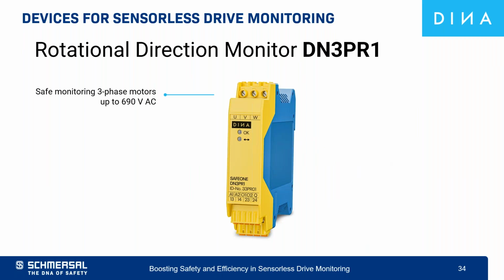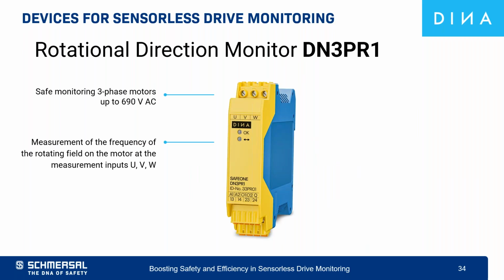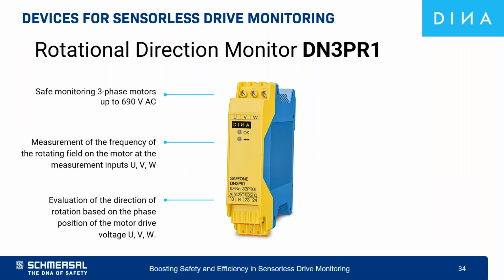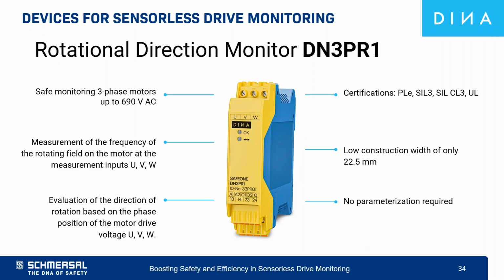This one can be used only for 3-phase motors. So you need all 3 phases due to the operational principle, because as Samuel explained already, we measure the frequency of the rotating field and then we evaluate the rotational direction based on the phase position of the individual voltages. And this is why we need all 3 phases. And of course, this device also has all the relevant certifications: PLE, SIL-CL3, and UL. It has the same dimensions as the other devices, and it doesn't require any parameterization. So this is really plug and play.